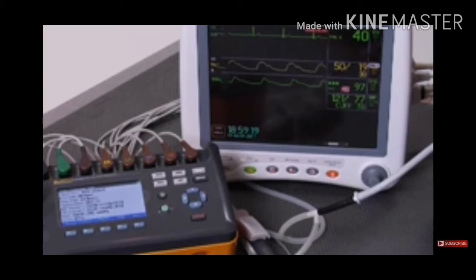You can see that the ECG rate on the monitor is already 40. Our invasive blood pressure is 50 over 19, very close to 50 over 20. Our cuff is working on getting its measurement, and the O2 sat is 97, right on with what we asked for, what we're simulating.